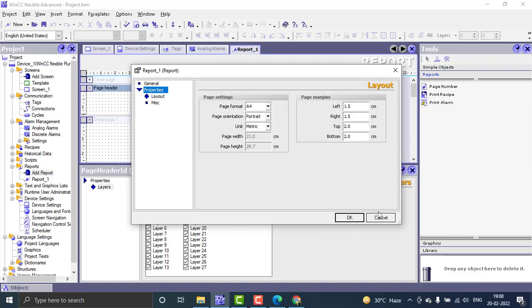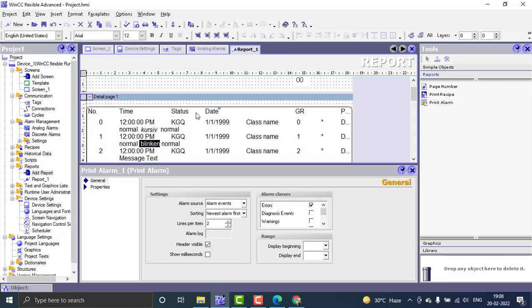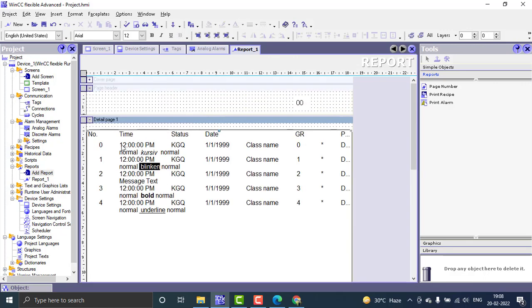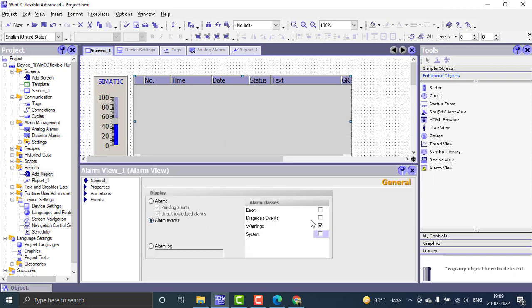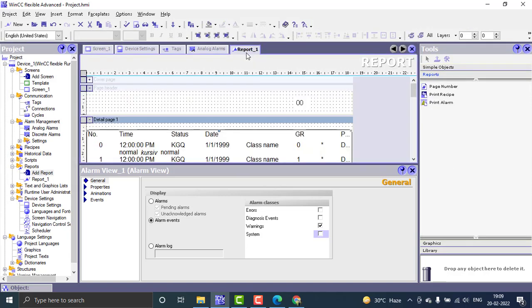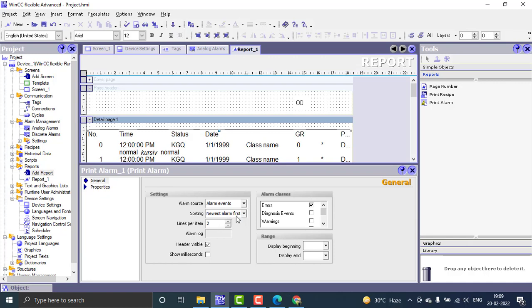Now I drag and drop a 'print alarm' object into the report. This defines the format in which alarms should be printed — including time, state, class name, and so on. Going to the properties, I set it to alarm events with warnings. In the report, you can choose alarm source, alarm events, or alarm log, and set sorting to newest alarm first.